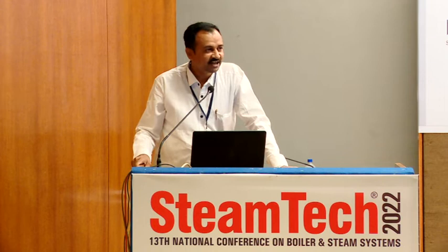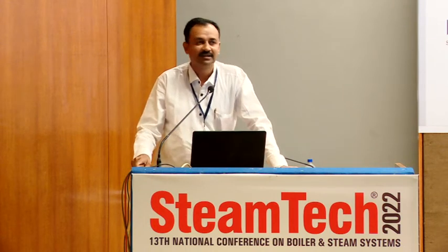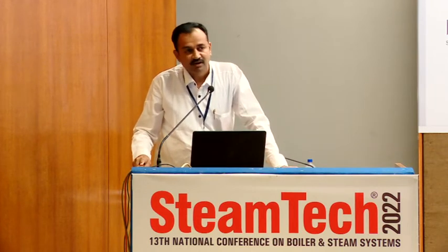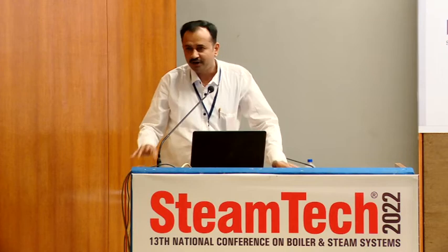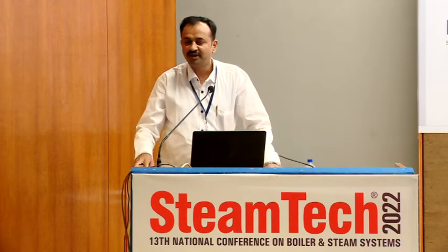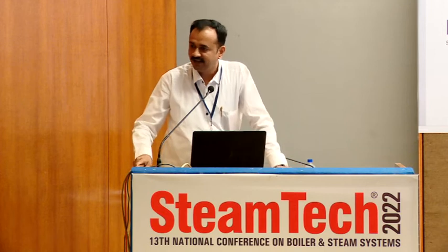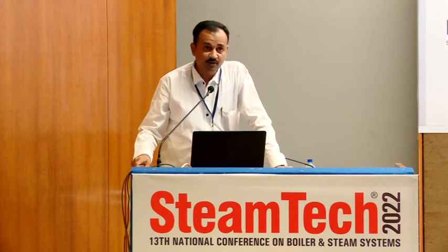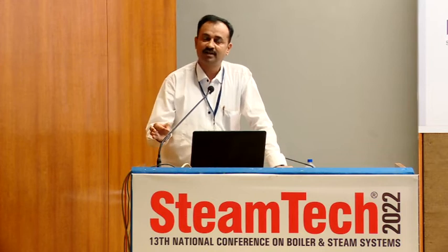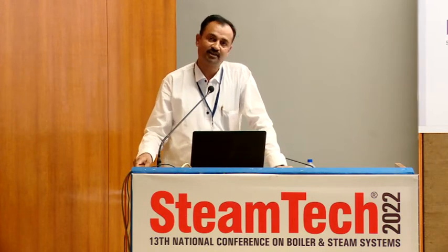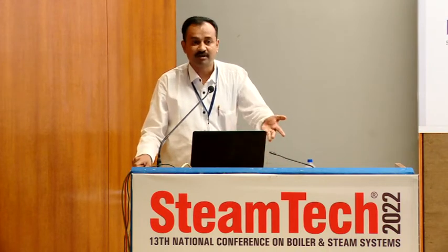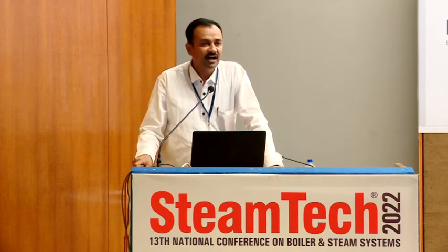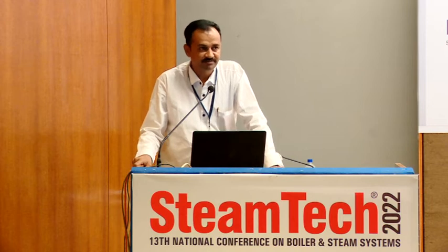A lot has been said about the boiler being the heart of the steam system. I will just crisply say that the fuel cycle and the water cycle are both the heart of the system, so I will not differentiate. I will not go into much more detail about the feed water tank and oil tank, all that. You can imagine that the fuel cycle is also the utmost part for the combustion side and the fuel efficiency side, and the water cycle is nothing but the feed water tank and the drum level that you are maintaining inside the boiler house. Both of them are very important, and they are the heart of the boiler house and the heart of the steam system, we can say.